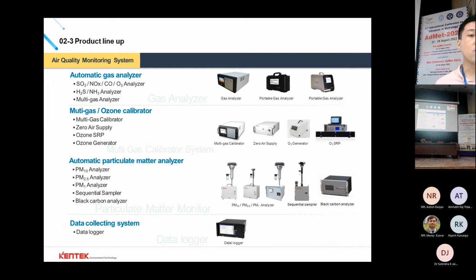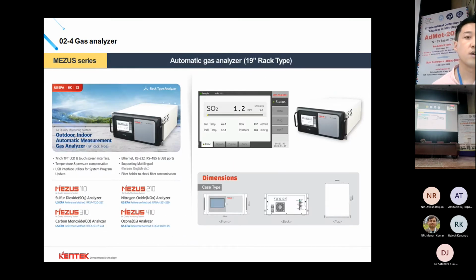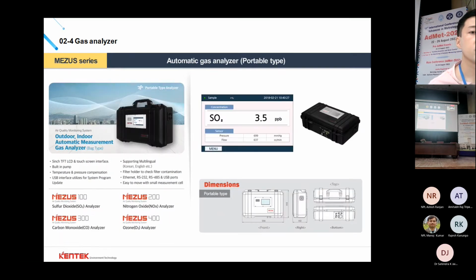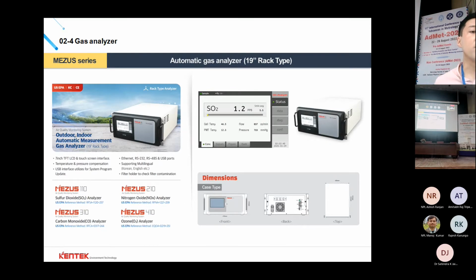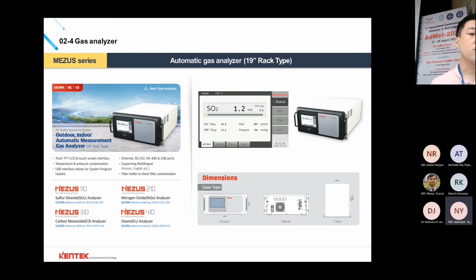Let's take a look at the products in more detail. This is our gas analyzers. Gas analyzers are made up of rack type analyzers and portable type analyzers. These analyzers are classified into SO2 analyzer, NOx analyzer, CO analyzer, and O3 analyzer. Looking at the measurement methods in more detail, the SO2 analyzer uses the UV fluorescence method, the NOx uses the chemiluminescence method, the CO uses the non-dispersive infrared method, and the O3 uses the UV absorption method. Most of these analyzers have acquired the US EPA certification.